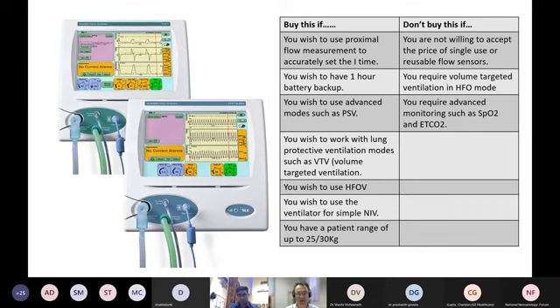So that step up in technology was integrated into the 5,000, which brought us this type of ventilator, which gives us all the functionality of a 2,000, plus all the flow sensor technology, which gives us lung protective ventilation modes such as VTV and PSV, and also the lung protective mode of ventilation, which is high frequency oscillation ventilation. So this is a technological step forward and brings high frequency oscillation into the NICU as well.